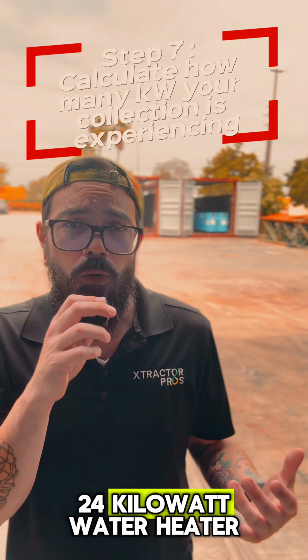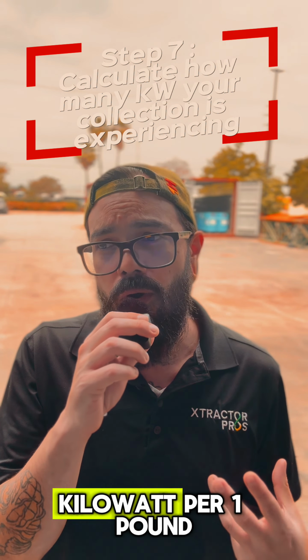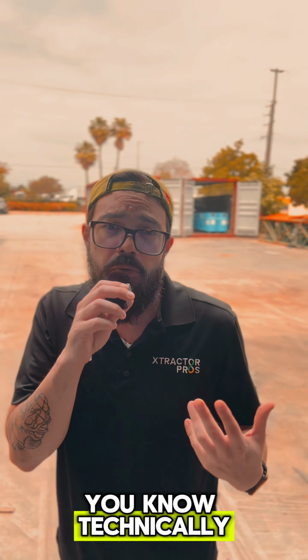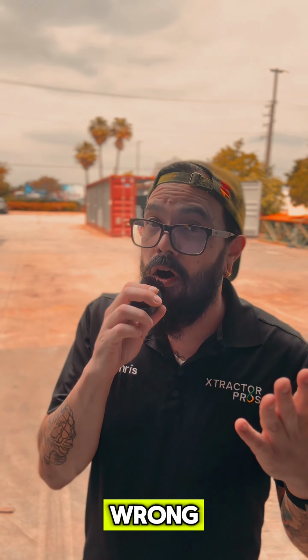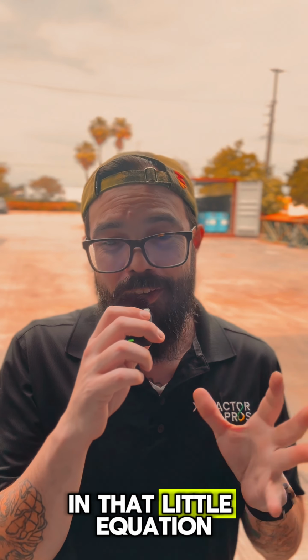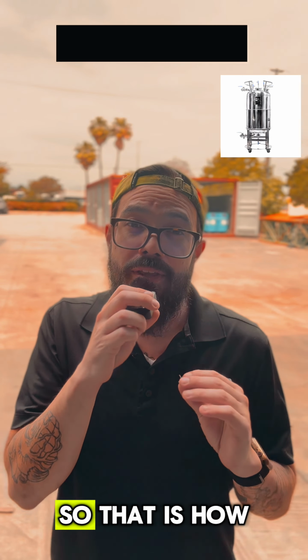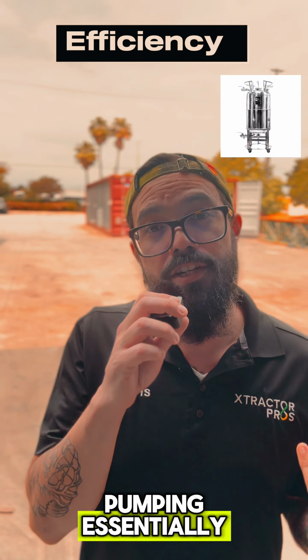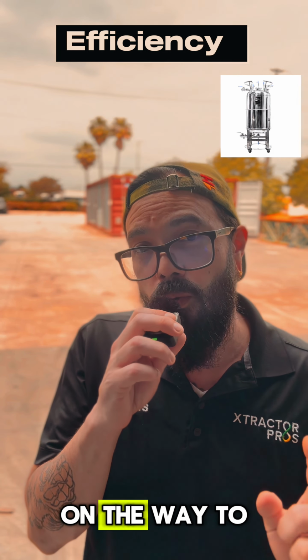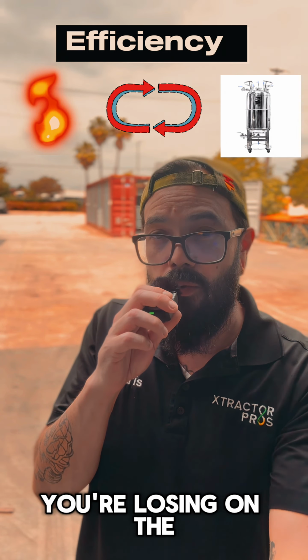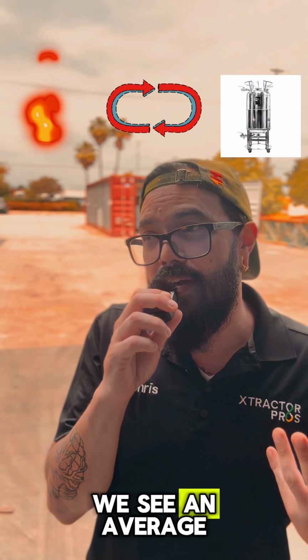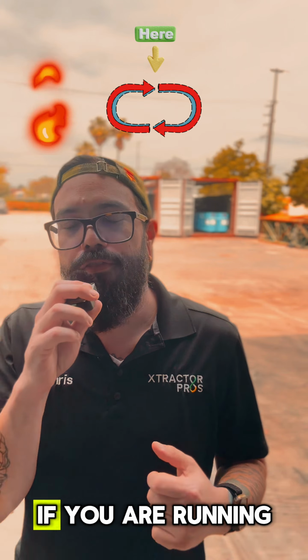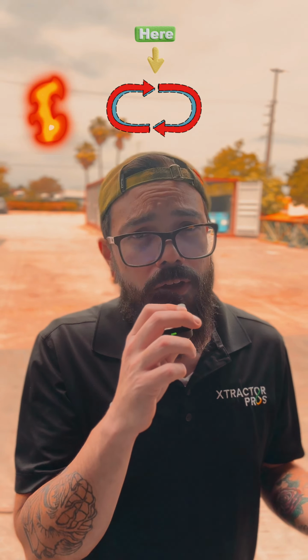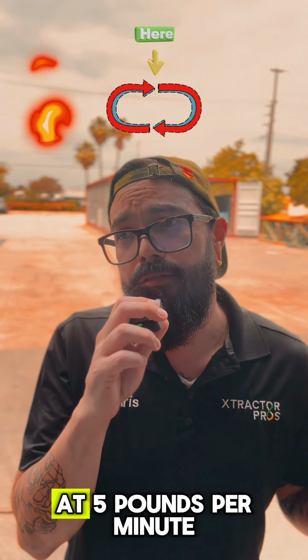If you have a 24 kilowatt water heater and you are abiding by the 4 kilowatts per 1 pound of butane recovery, technically we should be seeing 6 pounds a minute from a 24 kilowatt heater, right? Wrong. The thing we're not accounting for in that little equation is efficiency. That is how fast the water's pumping, and how many kilowatts you're losing on the way to the vessel and on the way back. Most of the time we see an average of 4 to 5 kilowatts per pound if you're running your heater at maximum. With a 24 kilowatt heater, most likely you're going to top out at 5 pounds per minute, usually about that 20 kilowatt range. That's the average, right?